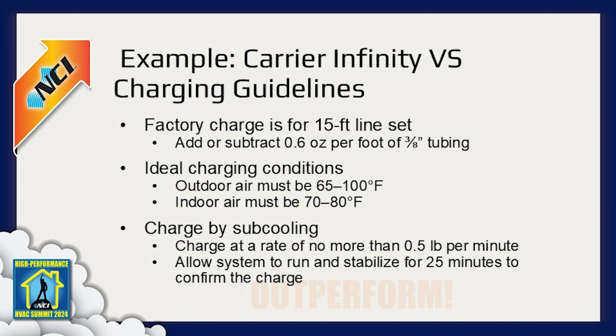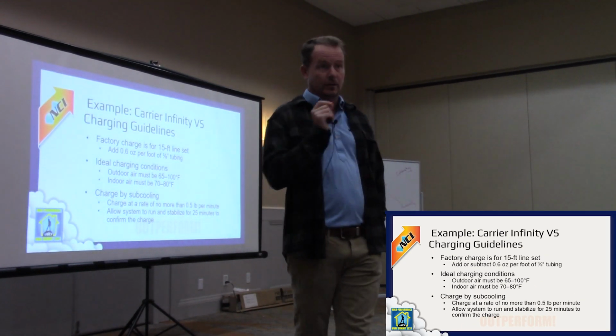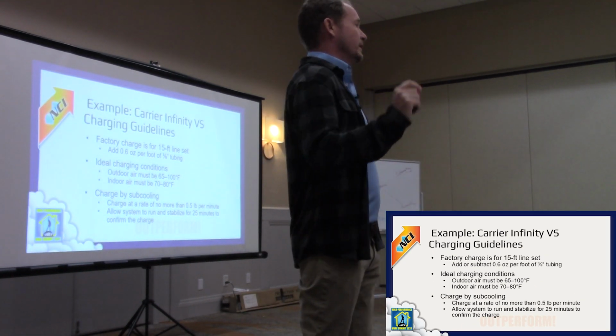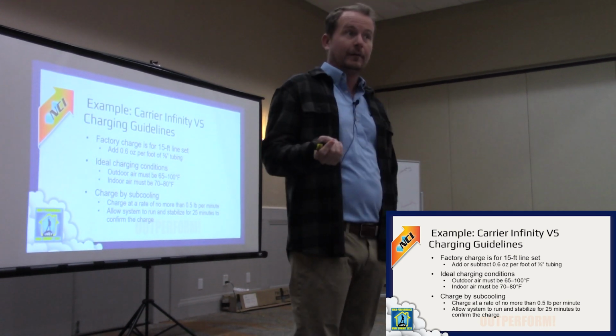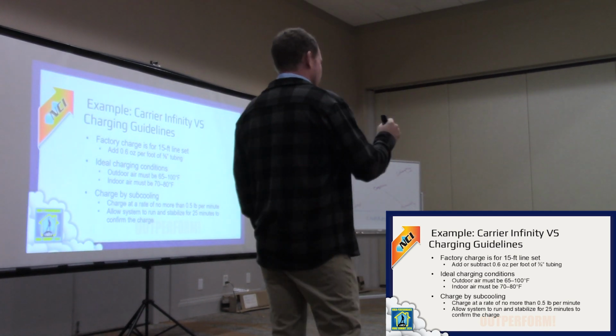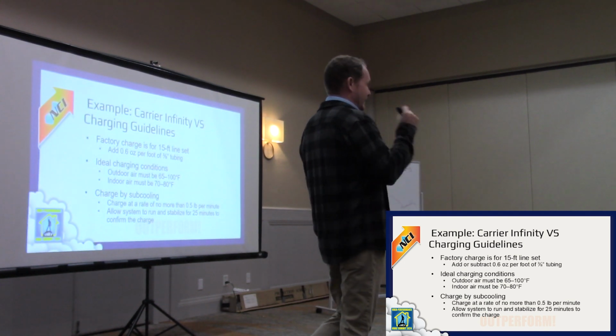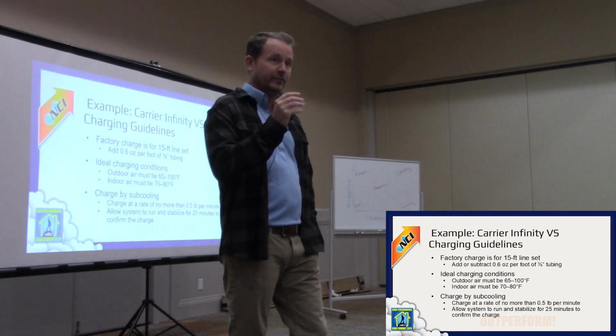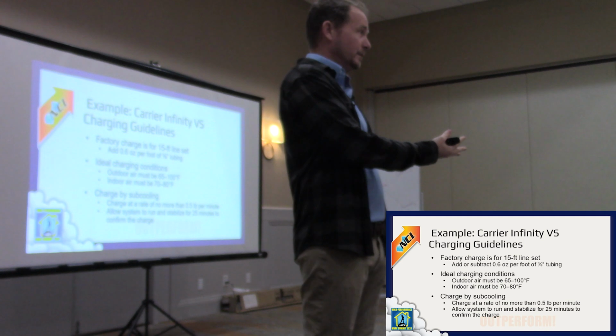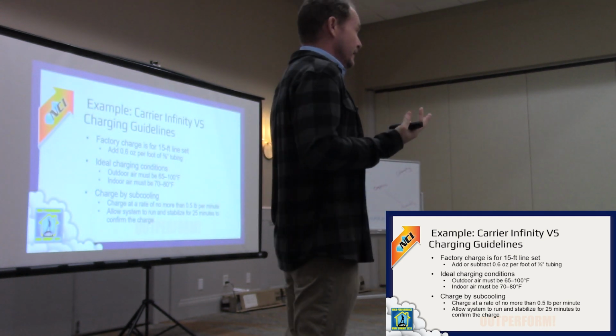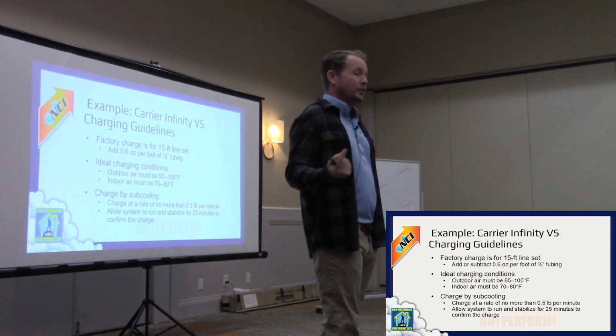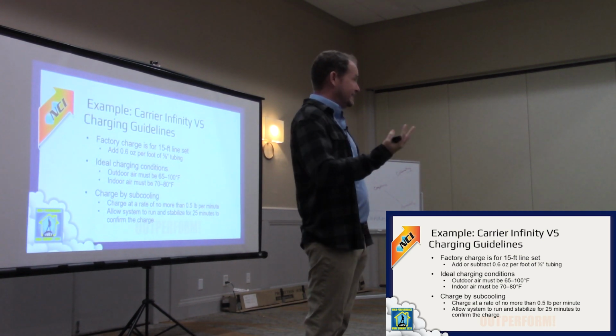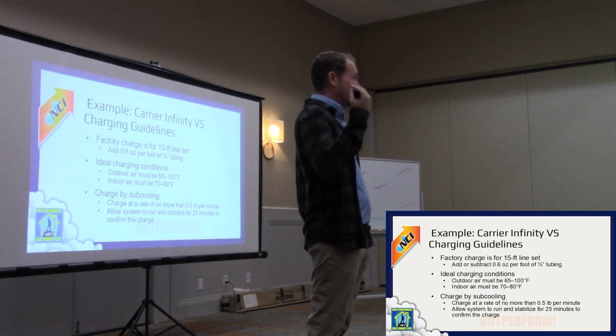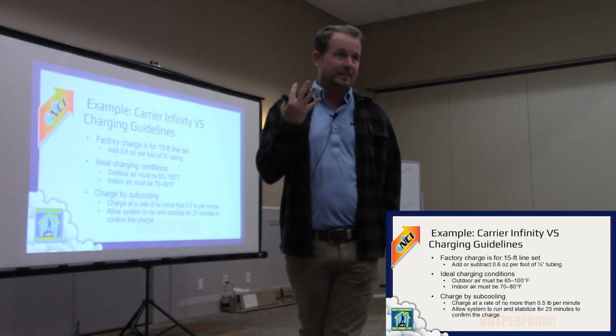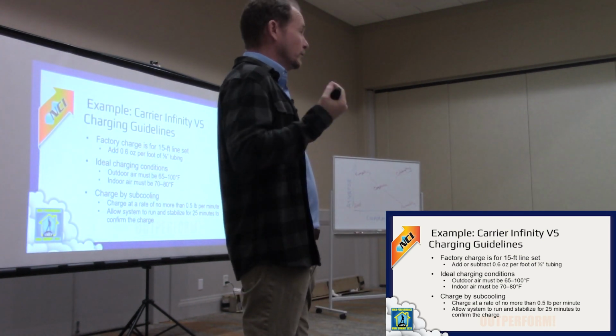When you are charging, this is key for all equipment but especially inverter-driven equipment with an accumulator. When adding refrigerant into the suction line on an operating system, which is the right way to do it, and you're adding liquid, you need to do it slowly and let it stabilize, especially with an accumulator. Think of what an accumulator is: it's in the suction line right before the compressor, it holds refrigerant, catching liquid refrigerant before it goes into the compressor. So when you put liquid refrigerant in that suction line and it dumps into the accumulator, it takes a while for that to circulate. It doesn't just go right through like it used to. There's an adjustment time that has to happen, and if you get impatient, you will overcharge it.